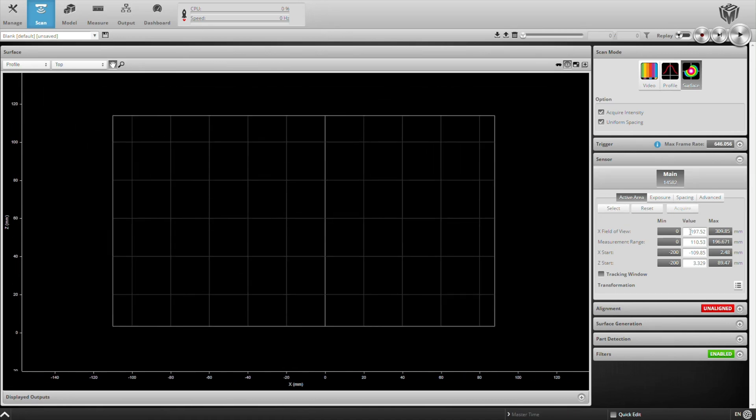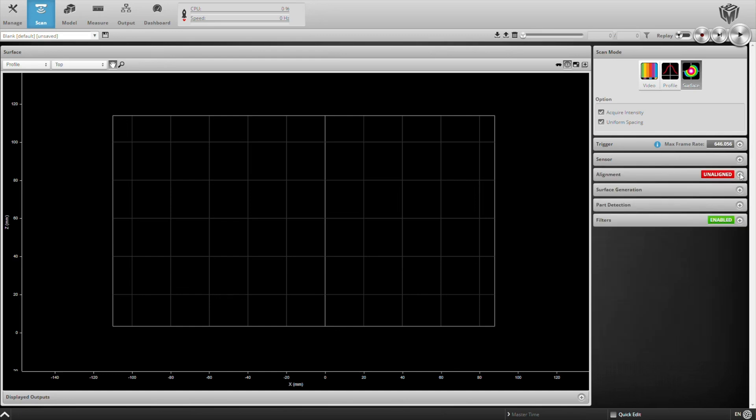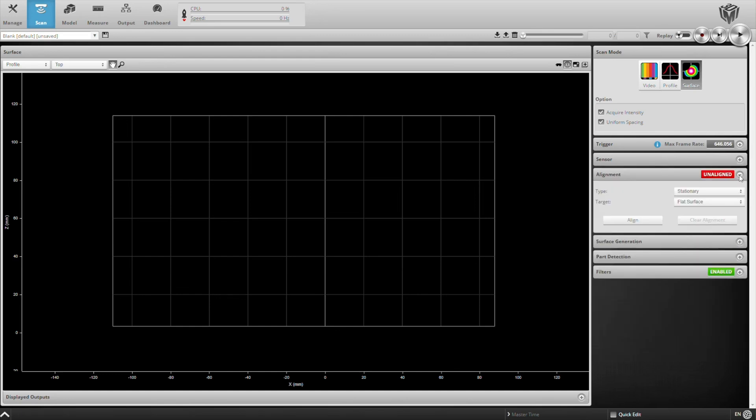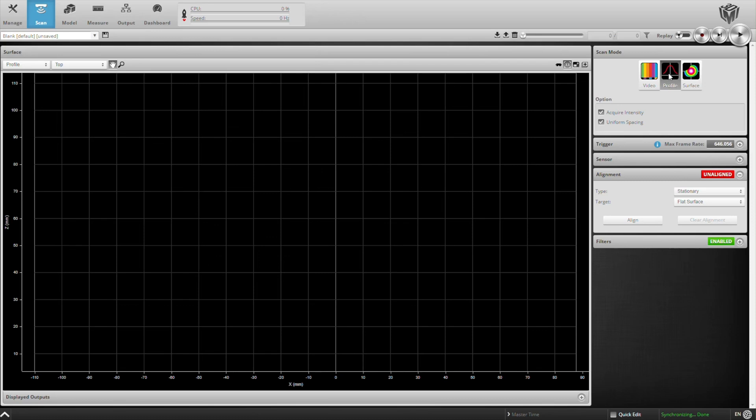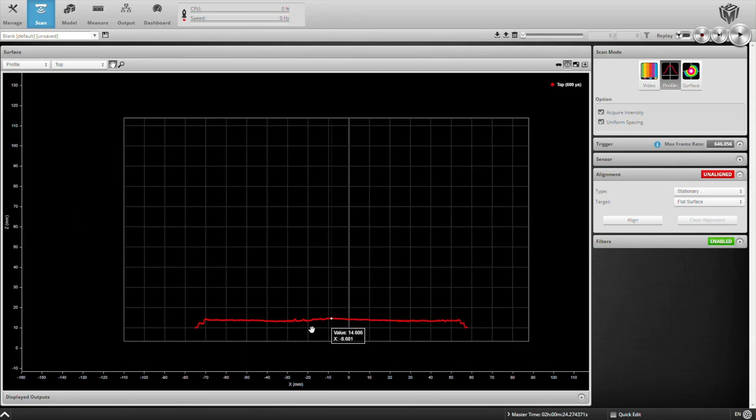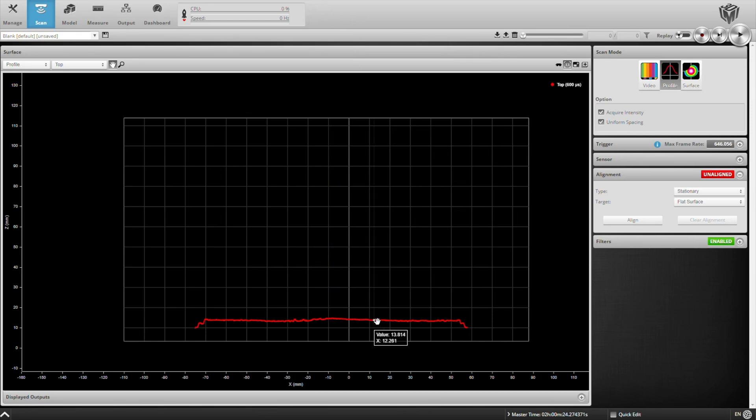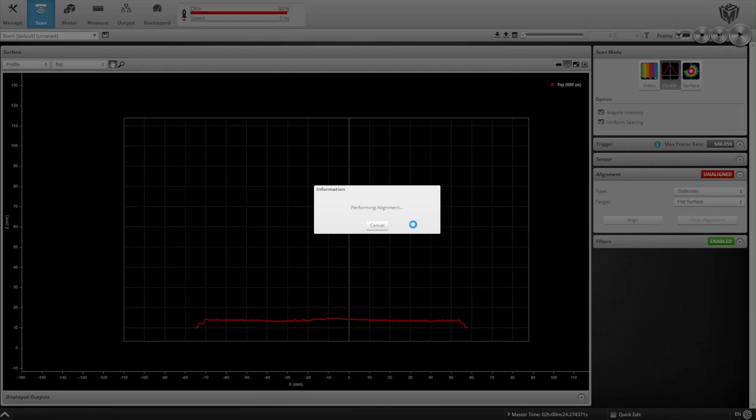Next, we're going to perform an alignment. Now, LMI's 3D sensors come factory calibrated, meaning you don't need to calibrate them in the field like you would with traditional 2D sensors using checkerboard or an array of dots. All values are displayed in millimeters. As you'll see here, when I hover over a profile, the value that's shown is in millimeters. And my axes, my X and Y axes, are in millimeters as well.